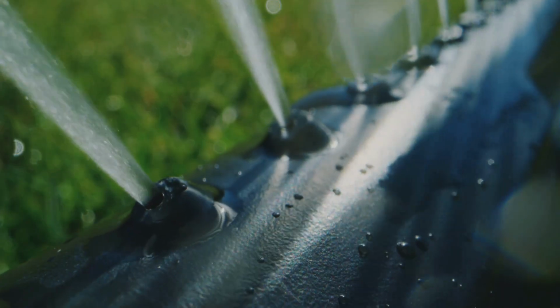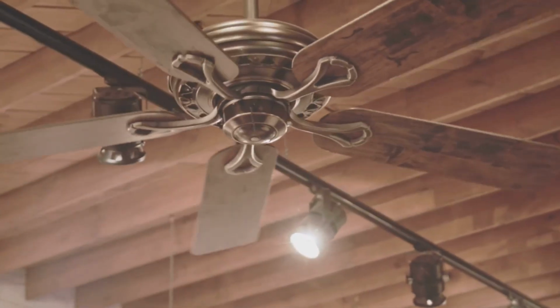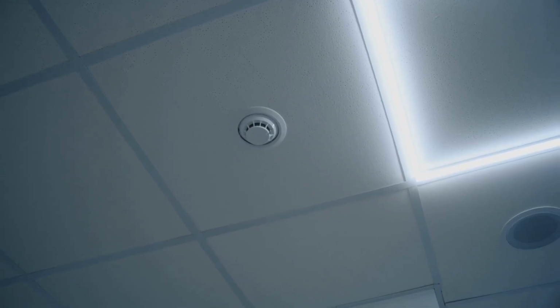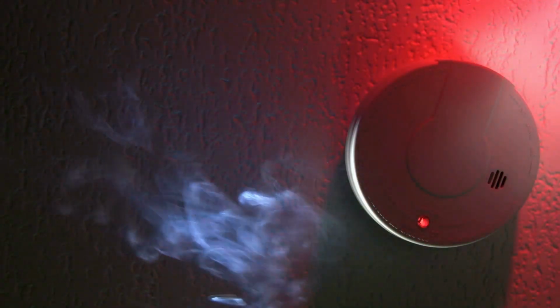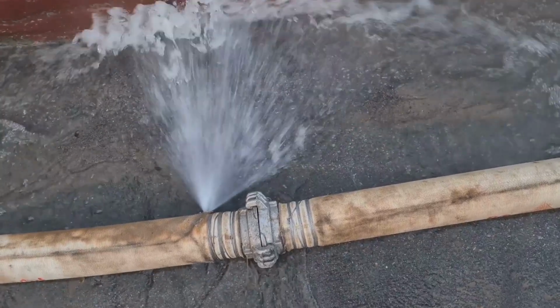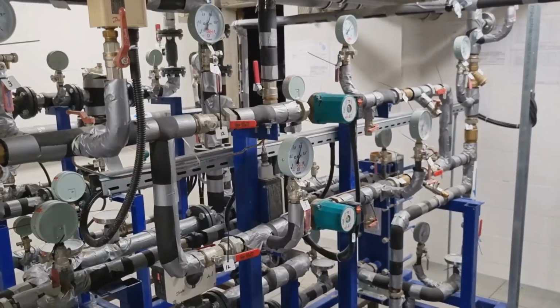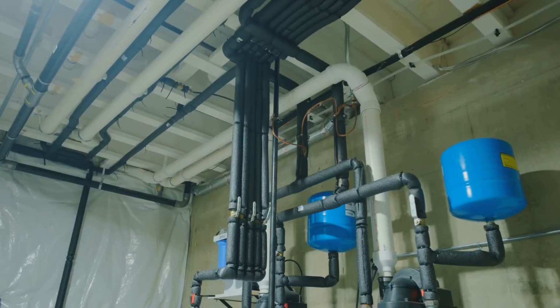This is one of the most important things to understand. Fire sprinklers do not react to smoke. They do not react to alarms. They react to heat. That means water is released only where the fire is actually hot enough to trigger it. Once the sprinkler opens, water flows immediately. But that water isn't coming from nowhere. It's already in the system.